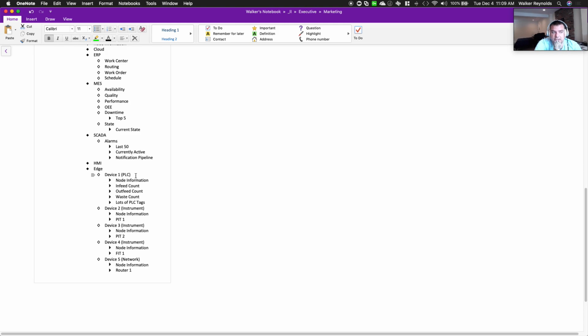The first device would be the PLC. That PLC, we have information about that node, the health of that PLC. We could have in-feed count come from that PLC, out-feed count, waste count, and also any of the calculated values the PLC produces. But what we wouldn't want to do is get our instrumentation values from that device, because we can get them from the instruments directly into our namespace.